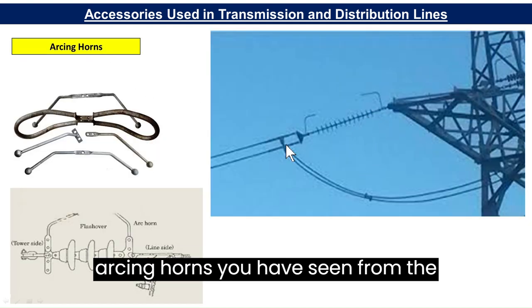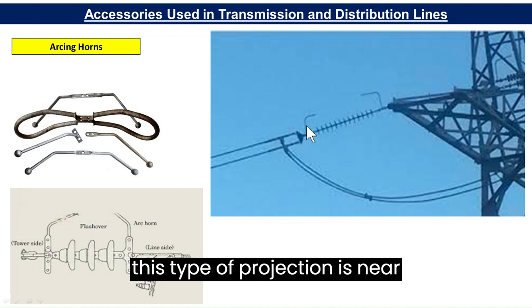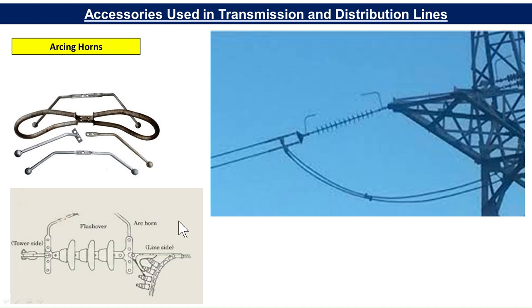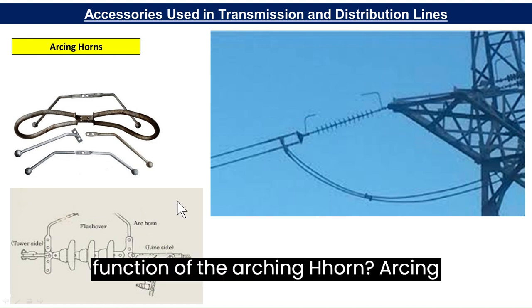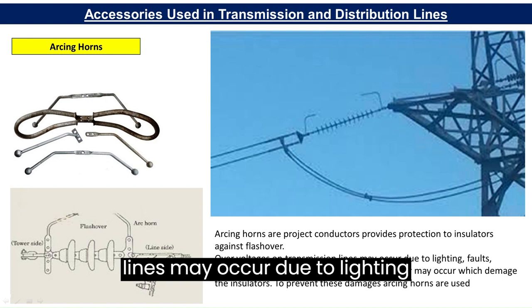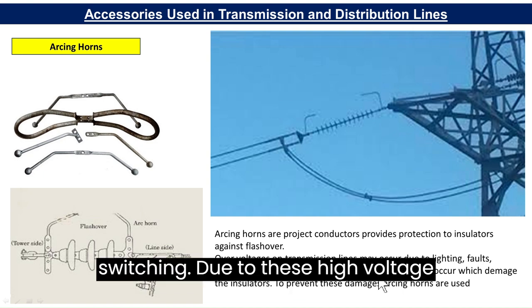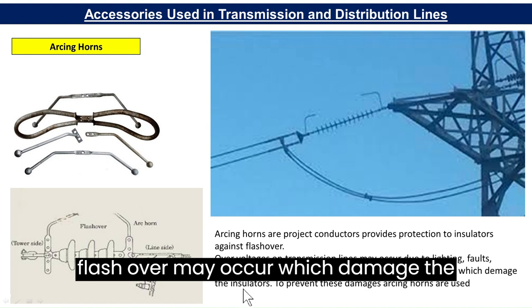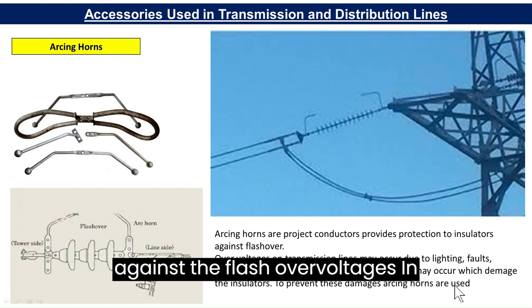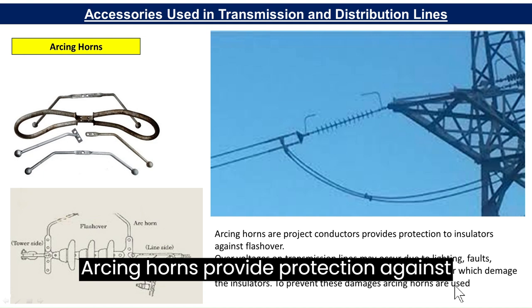Then there are arcing horns. You have seen these conductor projections near suspension insulators on various transmission lines. Arcing horns are projected conductors that provide protection to the insulators against flashover. Overvoltage on transmission lines may occur due to lightning faults or switching, which can cause flashover and damage the insulator. To prevent this damage, arcing horns are used. In insulators, there are two types of fault: flashover and puncture. Arcing horns provide protection against flashovers.